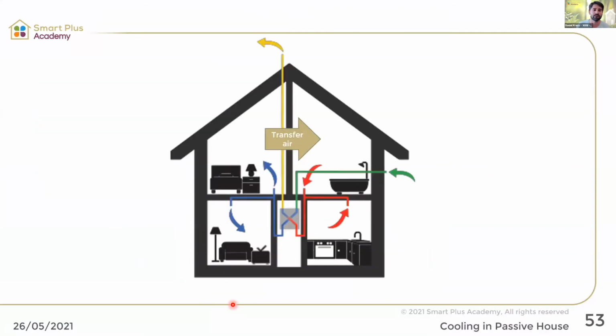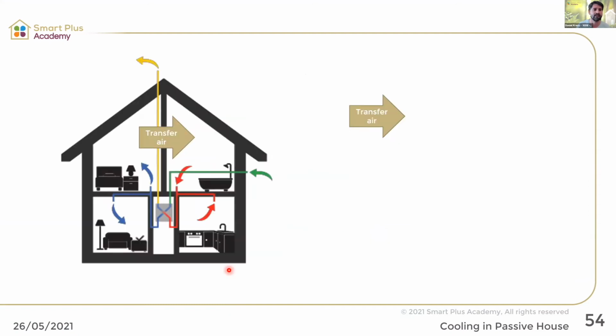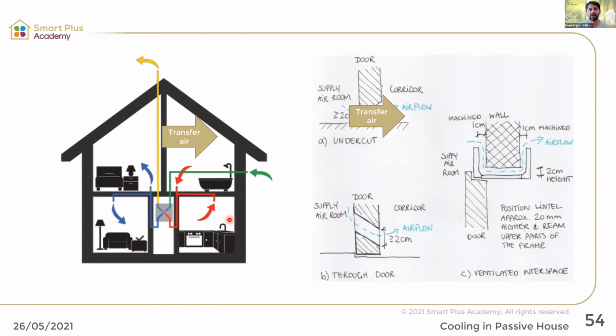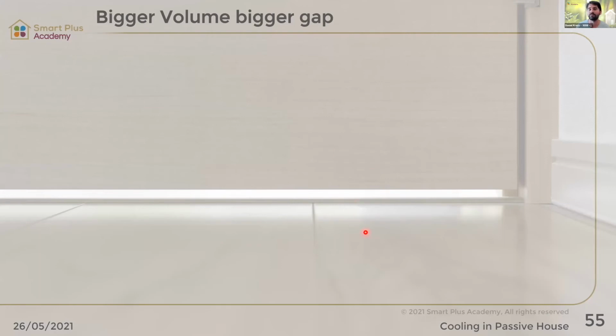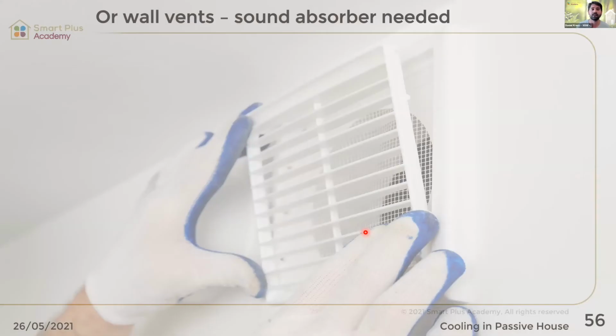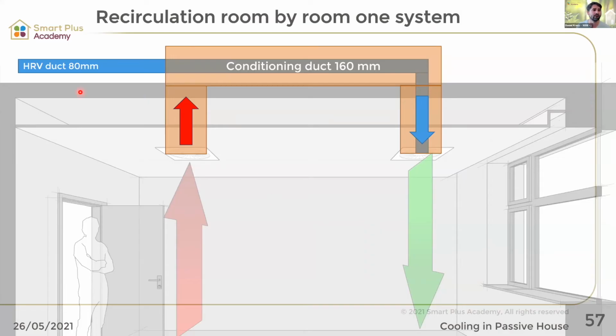Yeah, if we use the typical design approach of passive house, then we're having a transfer from one room to the other. We have supply rooms, we have extract rooms, and the air needs to move from one place to the other. So underneath our door, the gap needs to become bigger. So this would be the way it looks, or maybe even bigger depending on the airflow. Or we need vents in the walls, but now a sound absorber is really, really needed. Another option is we only have our heat recovery ventilation duct coming and supplying air into the room. And now we have in the room an air intake, with a bigger duct, and then here the air outtake. And in this duct, we are now conditioning the air.